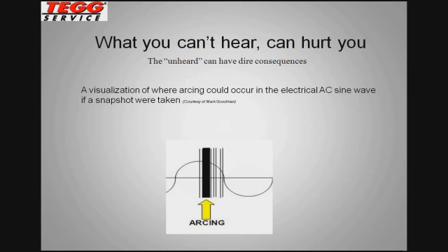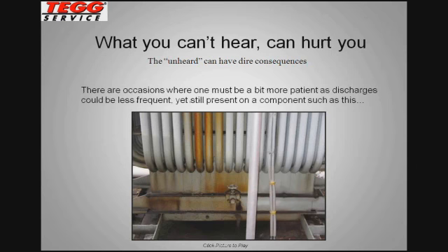There are occasions where a 5 or a 10-second recording may not be quite enough when it comes to arcing. In its very early stages, the arcing may not be frequent in its discharges, but it still could be present. And this is at the very early stages where insulation systems begin to fail. We'll put it up.